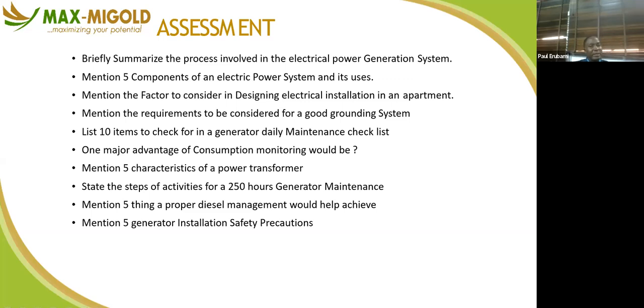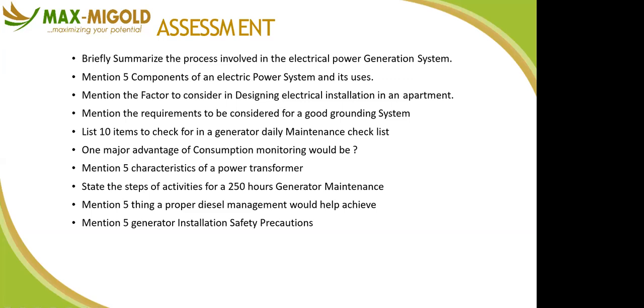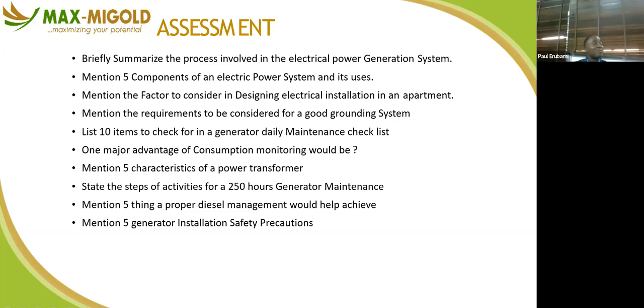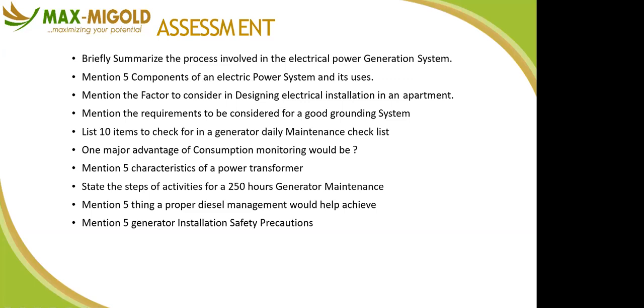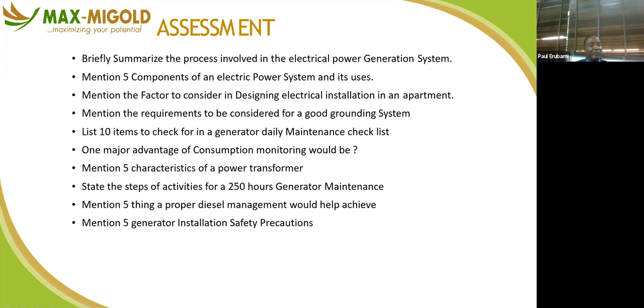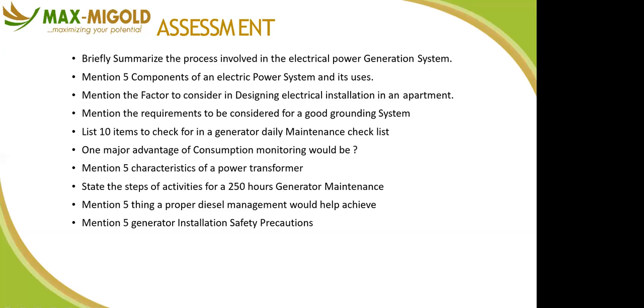In my class, I said there's room for expansion. When you get the total, let's say you arrive at 30 kVA in your calculation, you understand? Don't sit with 30 kVA. You have to go for about 45 kVA because of future expansion. Do you get? And you go for 45 kVA or so, because there will be room for modification. So don't just stick to the exact current load that you have determined. Is that taken? Yes, sir.